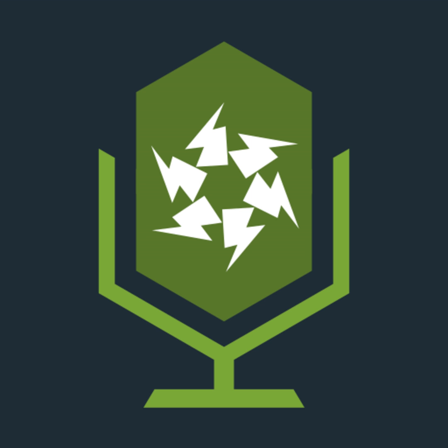512. Operational conditions and external influences. For all equipment, we must understand the operational conditions of the equipment, which we're going to list here, and the external influences relevant to the installation that the equipment must be selected against. So the operational conditions: we must know the voltage. It should be suitable for the nominal voltage Uo. So if it's a 230 volt nominal voltage, the equipment should be selected for that nominal voltage unless it's part of a different system, such as a SELV or PELV area.